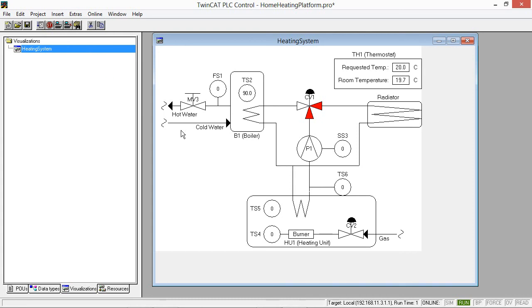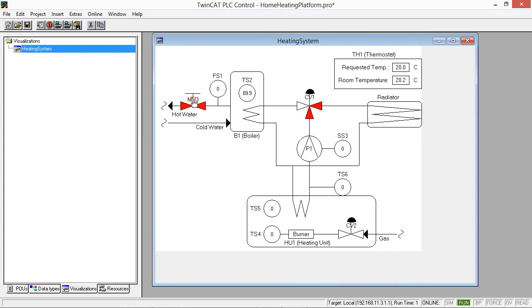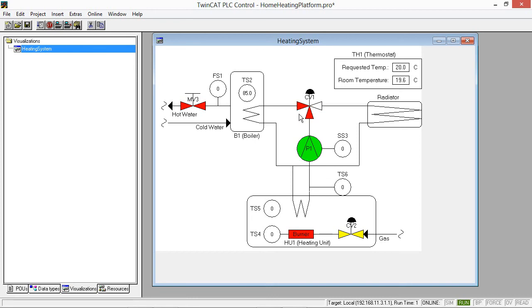And now we can log into the system and the system should be starting. We run it. And now if you go to the system we can basically see that it starts to work. Because the room temperature decreases. Or let's say I put the hot water running. So the temperature of the water in the boiler decreases because the cold water is coming to replace it. And when it reaches the cold enough, the burner goes on, the pump goes on, and the valve heats the boiler.